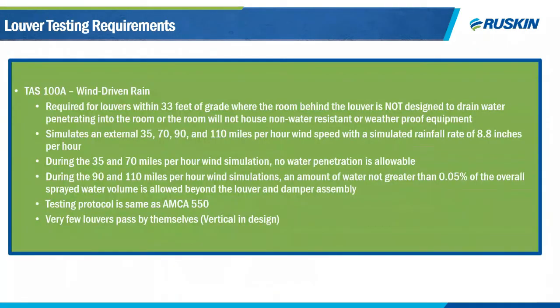TAS 100A is a high-velocity wind-driven rain test — essentially the predecessor to AMCA 550, developed after Hurricane Andrew hit Florida in the 1990s. It is very similar to AMCA 550 with some notable exceptions: at 35 and 70 mph, no water is allowed through the louver, and at 90 and 110 mph, only 0.05 percent of total water sprayed may pass through. The standard is being phased out due to the popularity of AMCA 550, and even Miami-Dade now accepts AMCA 550 as a substitute for TAS 100A.